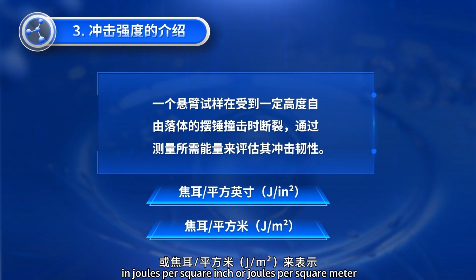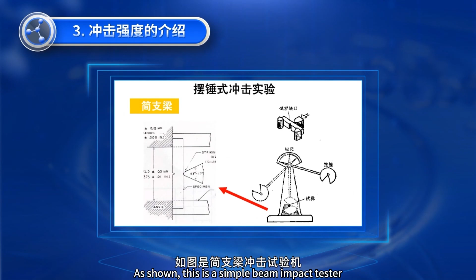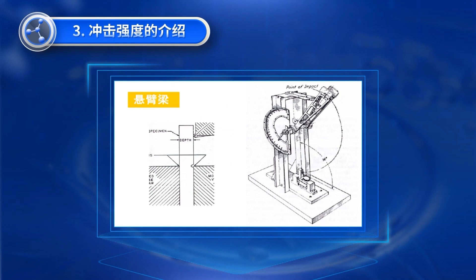Tests are typically conducted using cantilever and simply supported beam testers. A cantilever sample fractures when struck by a pendulum falling from a certain height. The energy required to break the sample is measured to assess its impact toughness. The results are typically expressed in joules per square inch or joules per square meter, which is known as the impact energy. As shown, this is a simple beam impact tester. This is a cantilever beam impact tester.